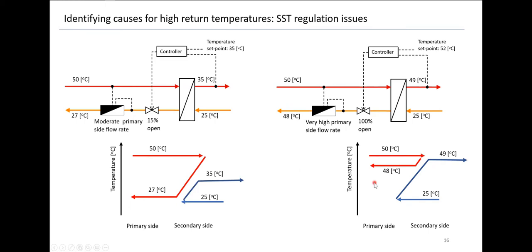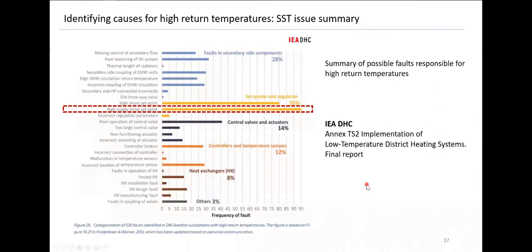This may seem silly, but a benchmark of more than 500 identified faults on substations in Sweden shows that incorrect set point regulation is the most frequent problem. It's simple to solve, but it happens often in practice.